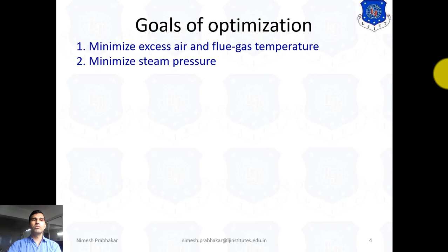Now the second one is to minimize steam pressure. That means inside the boiler drum, or inside the boiler, the pressure is minimized. So we can automatically increase the efficiency by reducing the pressure inside the boiler. There are a number of methods to minimize the steam pressure. The first one is to open up the turbine governors. The second one is to reduce the feed pump discharge pressure, and the third one is to reduce heat loss through pipe wall. We will discuss all three strategies next.